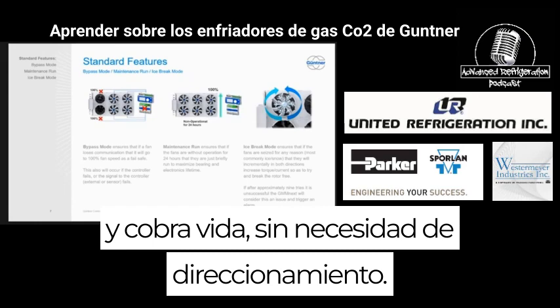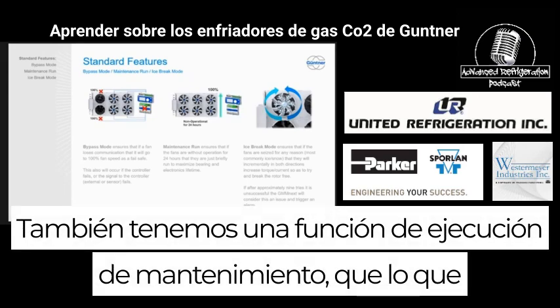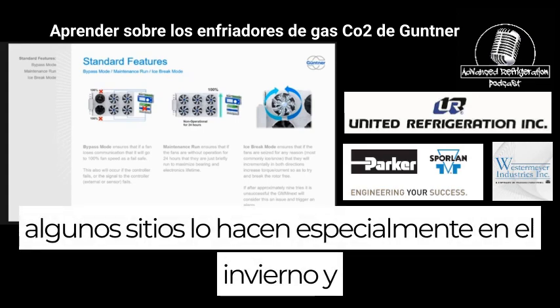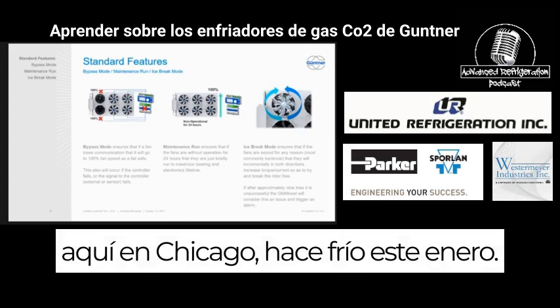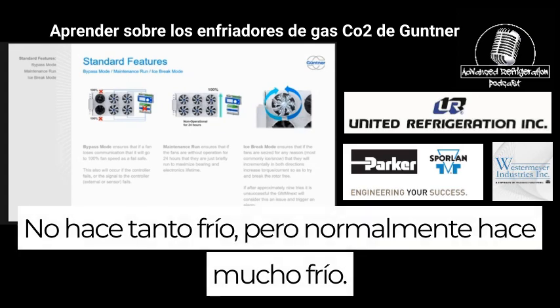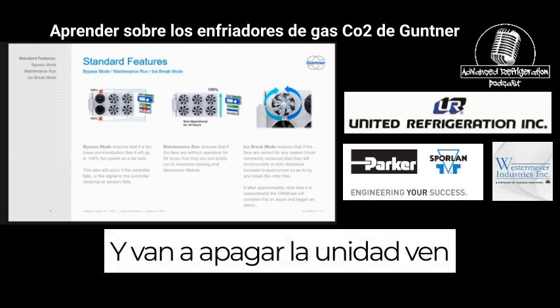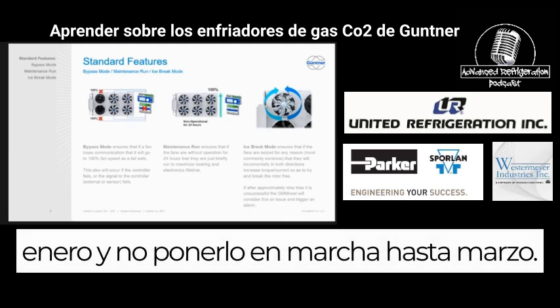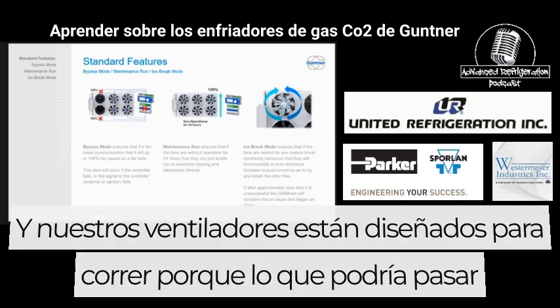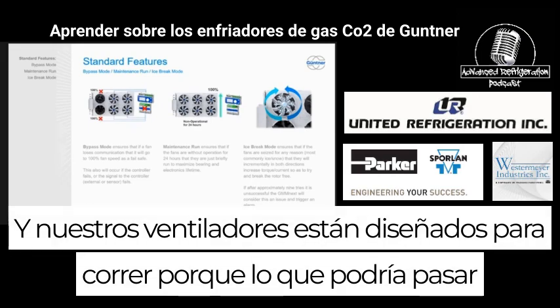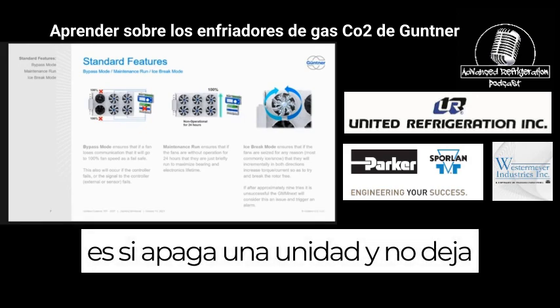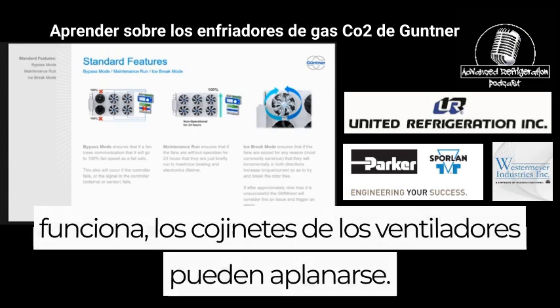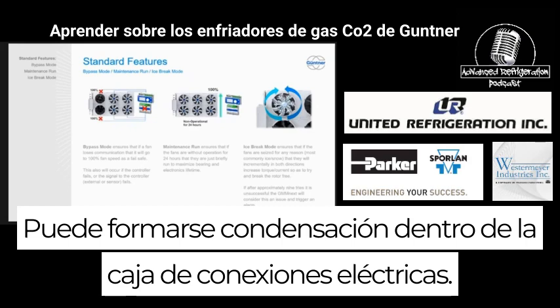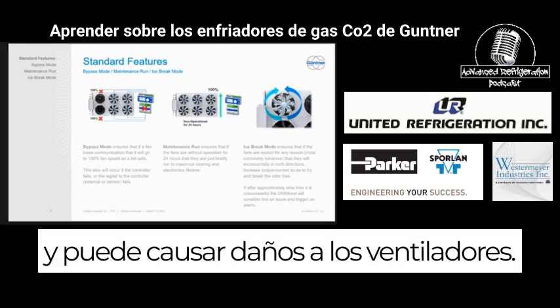No addressing necessary. We also have a maintenance run feature. What some sites do, especially in the winter, and up here in Chicago, it's cold. This January, it's not that cold, but it normally gets really cold. They will shut down a unit, come January, and not start it up until March. And our fans are designed to run. Because if you shut a unit down and you don't let it run, the bearings on the fans can flatten, and condensation can form inside the electrical terminal box and cause damage to the fans.